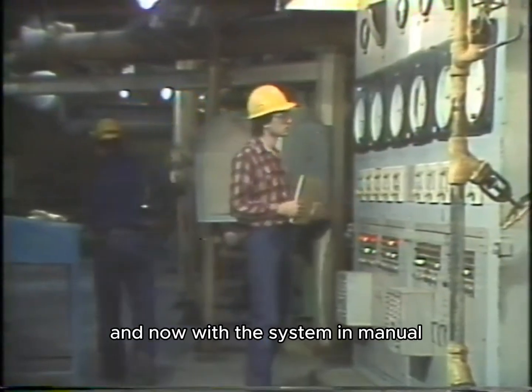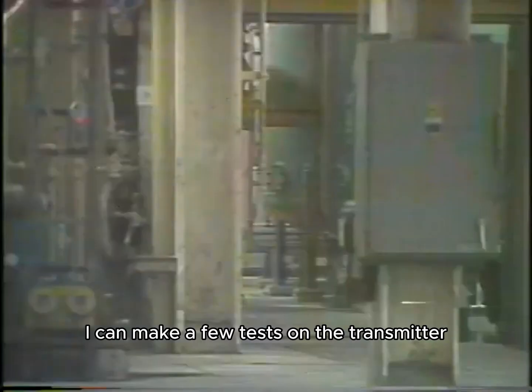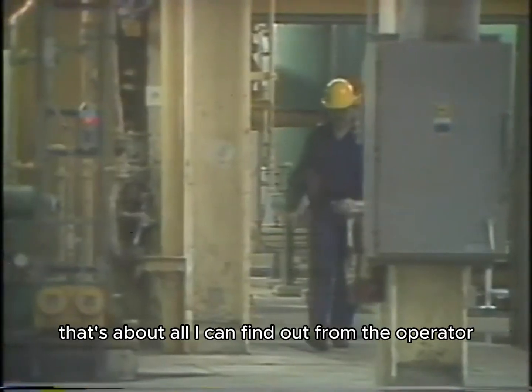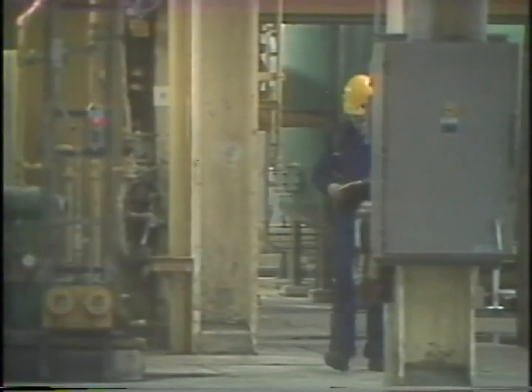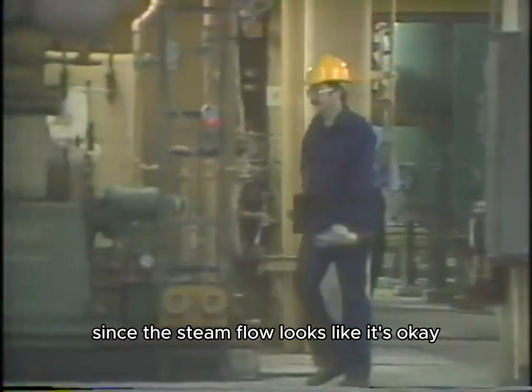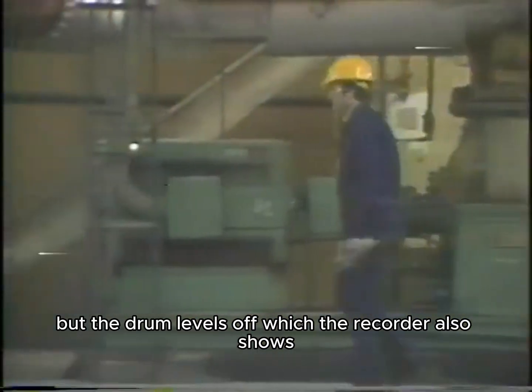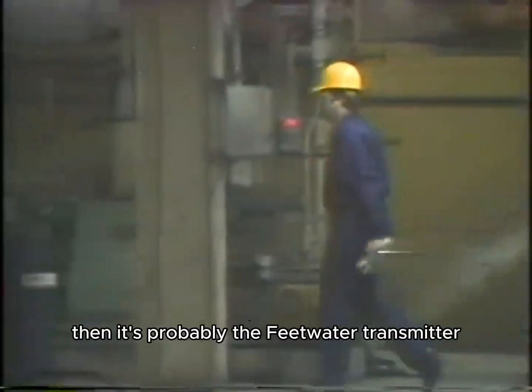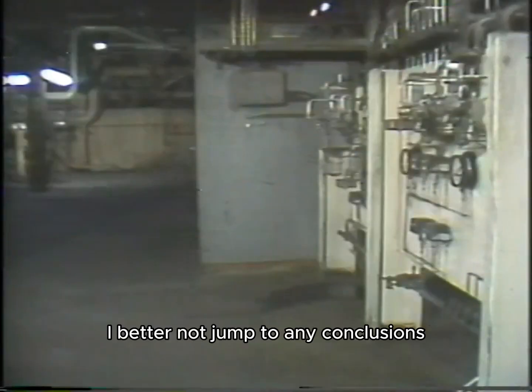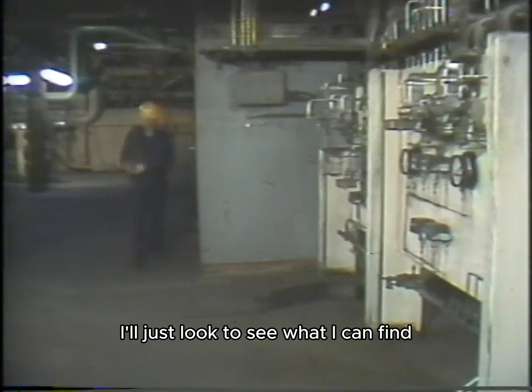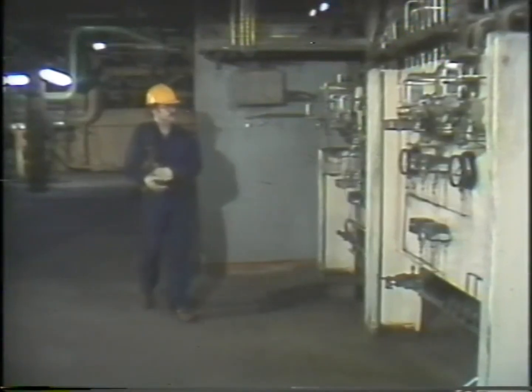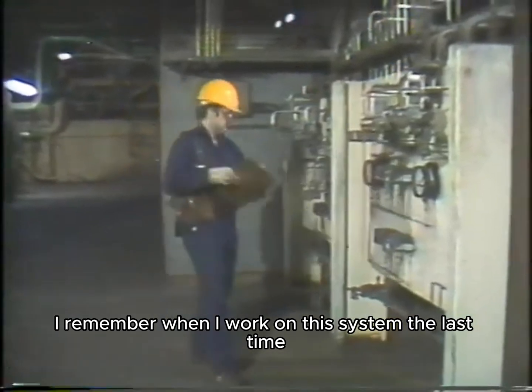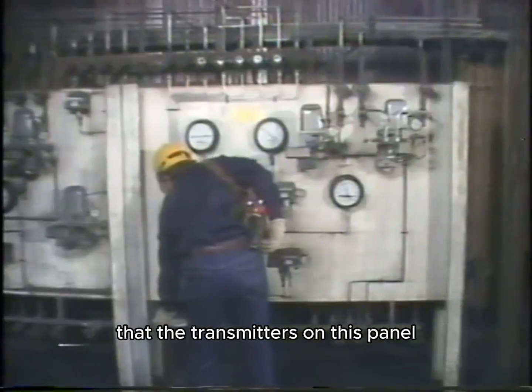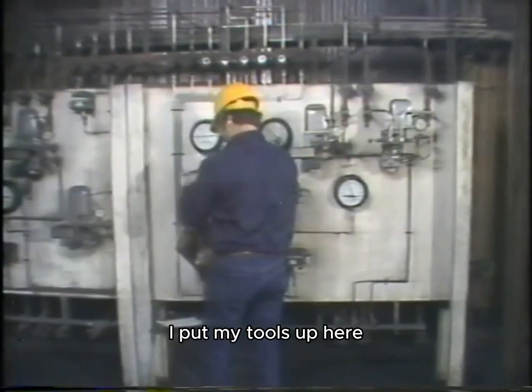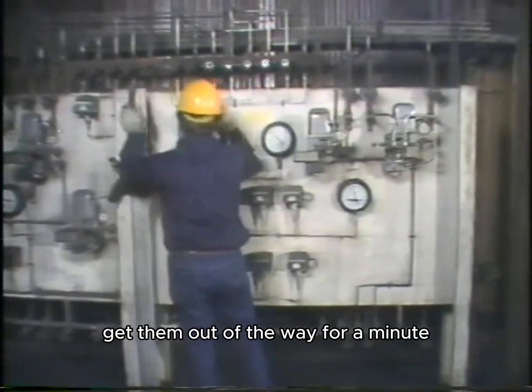Now with the system in manual, I can make a few tests on the transmitter. That's about all I could find out from the operator. Since the steam flow looks like it's okay, but the drum level's off, which the recorder also shows, then it's probably the feed water transmitter that's causing the problem. I better not jump to any conclusions. I'll just look to see what I can find. I remember when I worked on this system the last time that the transmitter's on this panel. I'll put my tools up here, get them out of the way for a minute.